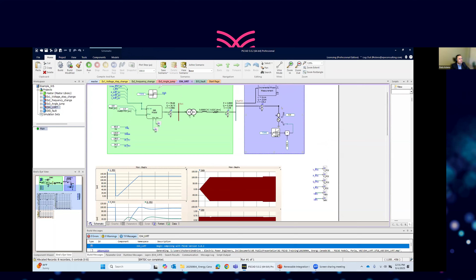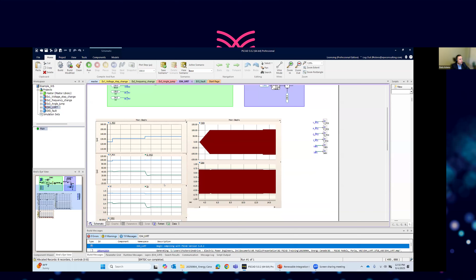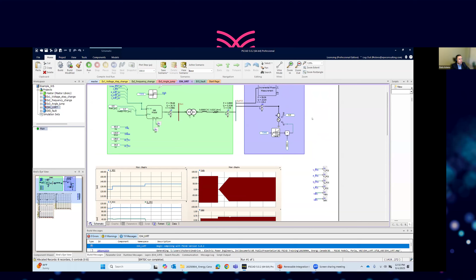And then this reactive power goes up, and after a while the voltage recovers and the active power starts to come back, because when reactive power is coming down, active power has more room. Here is the priority of the controller. Inside here is the Q priority. So we can see all these features and this performance by doing this kind of simple test to make sure of the behavior. For example, even when we bring the voltage back to 0.98 per unit, we can see that the LVRT loop does not freeze. It should go back to the lower value of reactive power. So all this performance needs to be tested before we start the actual test.